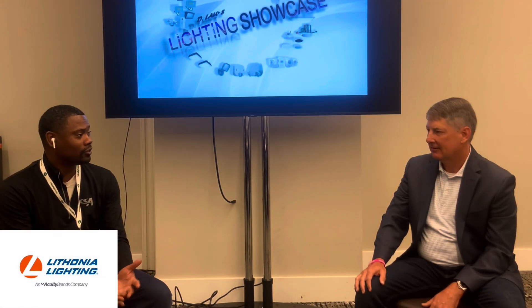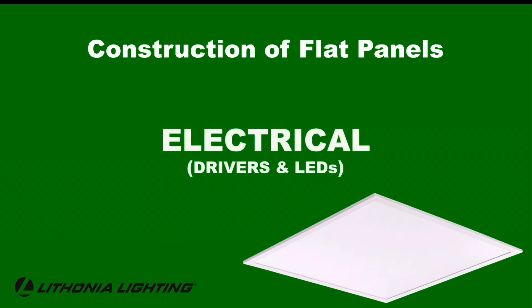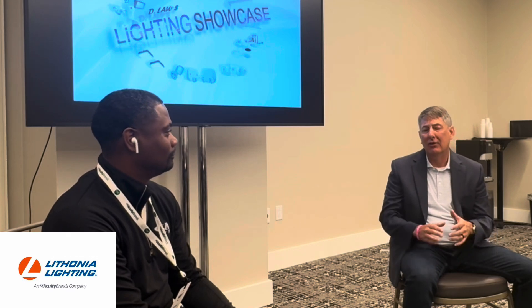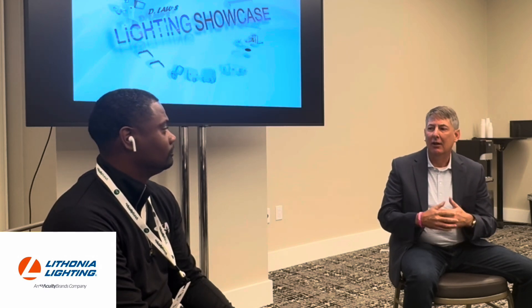So Tommy, we all know that all flat panels are not created equal. Can you tell me what makes the flat panels from Lithonia Lighting unique? Well, it's all about the construction. When you look at the construction of the panel, it breaks down into three categories: electrical, mechanical, and optical. Starting with electrical — at the heart of every panel there's a driver. Our drivers have typically more surge protection than what we see from our competitors. We also put isolated dimming leads into our drivers, and that's really important. The reason is, if you put a lot of panels on a circuit — certainly a dimming circuit — you can have some issues if you're using non-isolated dimming leads. So we isolate the dimming leads to make sure that voltage leakage on large runs is not a problem.